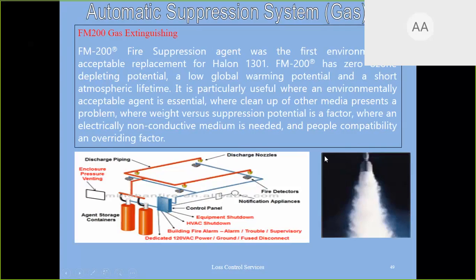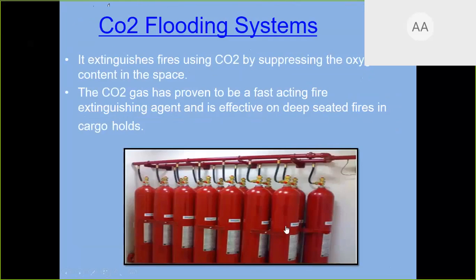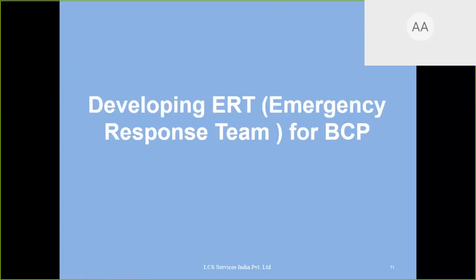Right? First, the siren will activate when the UV-IR sensor activates. It will give you an alarm so that if there is anybody inside the paint shop, he has to come out. And after 20 seconds, this CO2 cylinder will automatically dump all the CO2 inside the paint shop. The quantity of the CO2 is decided based on the volume of the paint shop area. How much is the top coat, how much is the base coat area, how much is the paint kitchen.